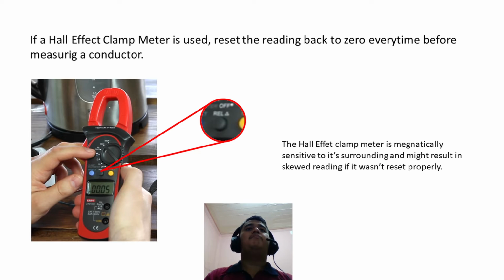If a Hall effect clamp meter is used, reset the reading back to zero every time before measuring a conductor. The Hall effect clamp meter is magnetically sensitive to its surroundings and might result in a skewed reading if it wasn't reset properly. Now I will pass it on to Hafiz Najmi, so he can explain how to measure alternating current.